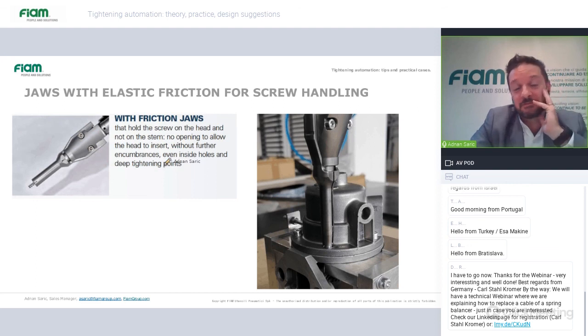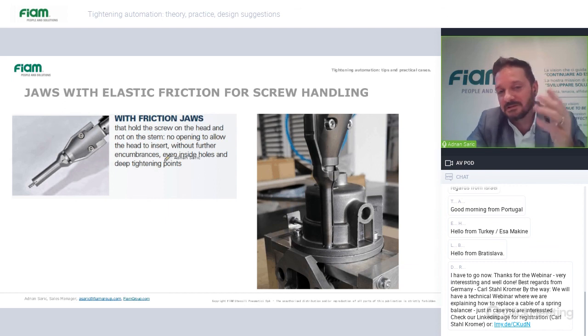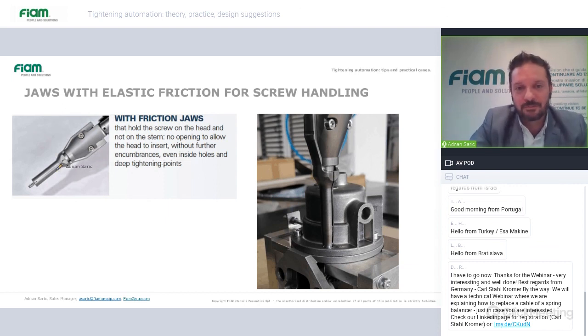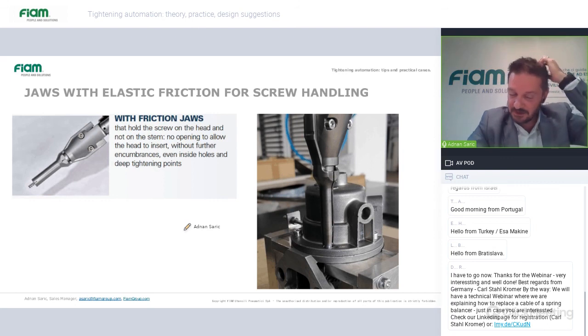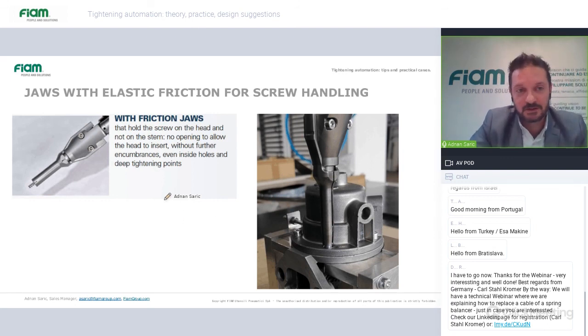Very often our competitors use the vacuum retention. Vacuum retention, of course, is the easiest way to hold the screw and to deposit in deep. But it is also risky because, as you said, dirt is always present and the maintenance is very, very often required. For this reason, we use this solution, which is not the pipe, but it's the screw which is being delivered with screw elastic friction by the bit. So we have full control of the screw until the screw deposit. In this way, we also guarantee the axial exit of the screw.